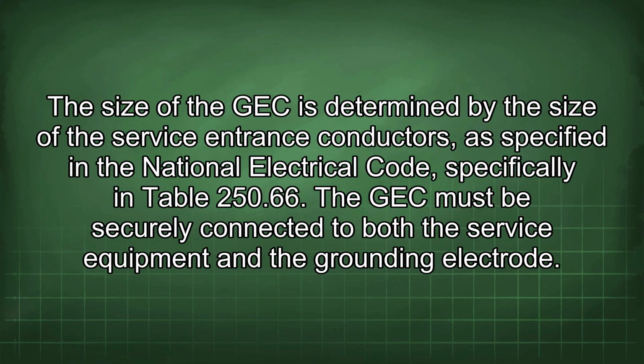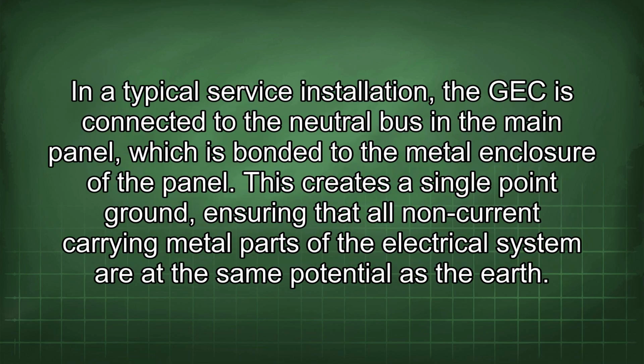The size of the GEC is determined by the size of the service entrance conductors, as specified in the National Electrical Code, specifically in Table 250.66. The GEC must be securely connected to both the service equipment and the grounding electrode. In a typical service installation, the GEC is connected to the neutral bus in the main panel, which is bonded to the metal enclosure of the panel. This creates a single-point ground, ensuring that all non-current carrying metal parts of the electrical system are at the same potential as the earth.